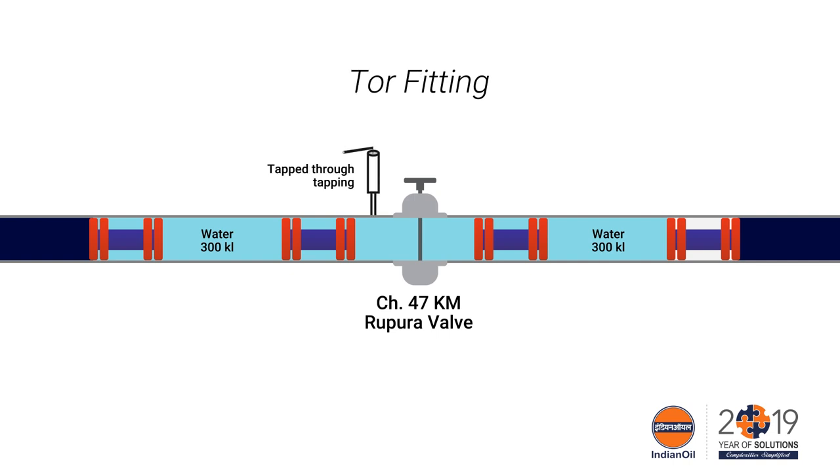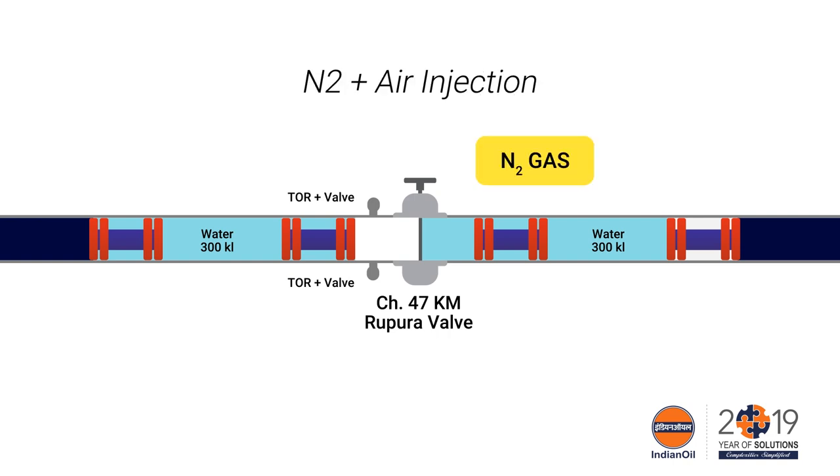Needful modifications like removal of the flapper of NRVs at Viramgam station was carried out, and draining of water between the third pig and Rupura valve was carried out through TORs. Nitrogen was pumped through the TOR and crude was received back in the Viramgam tank.